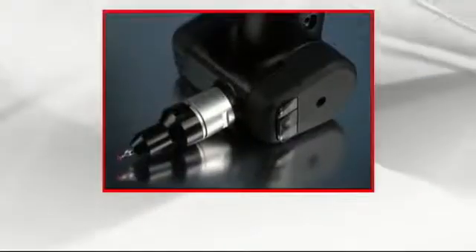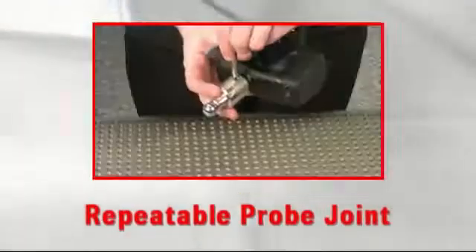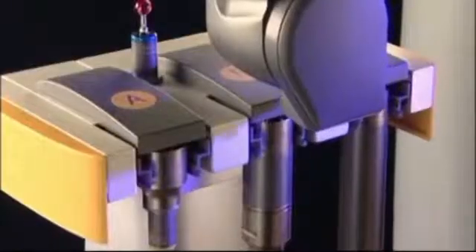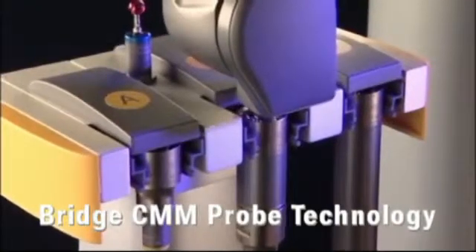The Romer Absolute Arm includes a bridge CMM class kinematic probe joint. Simply connect a new probe to the head and the arm automatically recognizes its type and recalls the probe calibration data. Just as on a bridge CMM, probes can be changed on the fly without recalibrating.